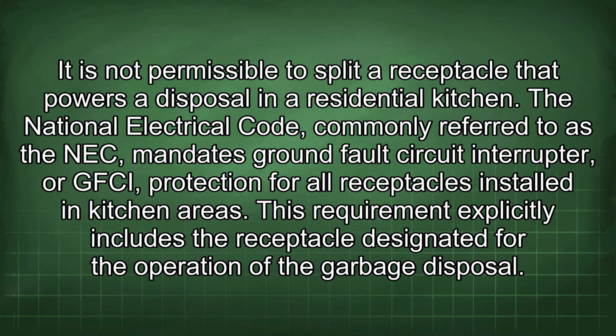It is not permissible to split a receptacle that powers a disposal in a residential kitchen. The National Electrical Code, commonly referred to as the NEC, mandates ground fault circuit interrupter, or GFCI, protection for all receptacles installed in kitchen areas. This requirement explicitly includes the receptacle designated for the operation of the garbage disposal.